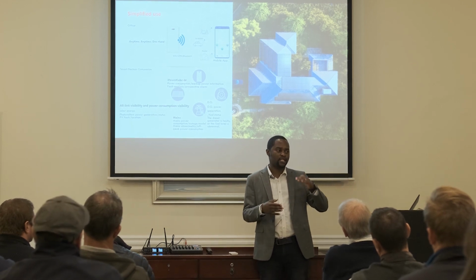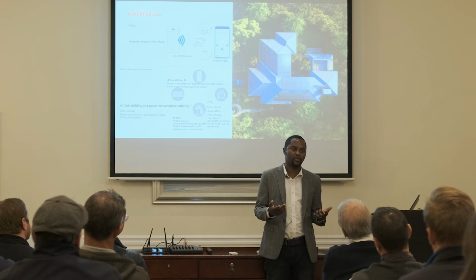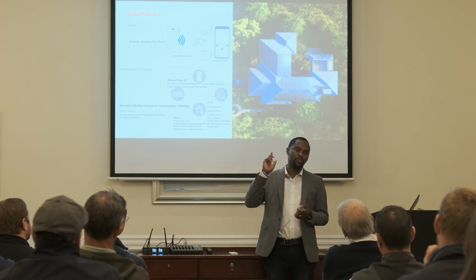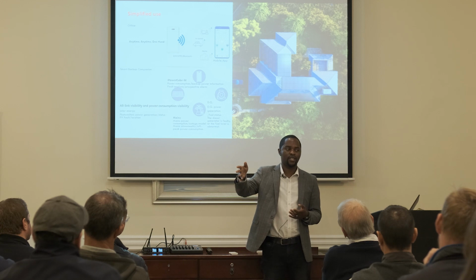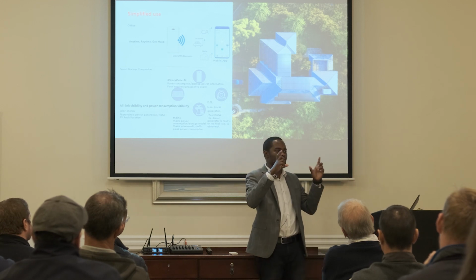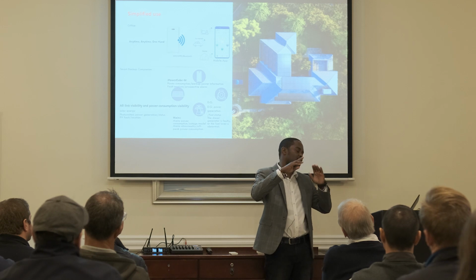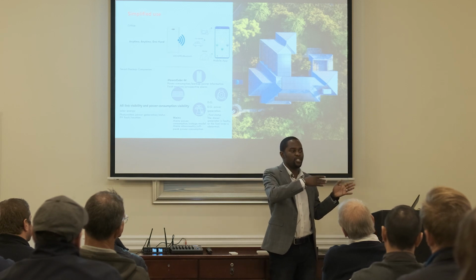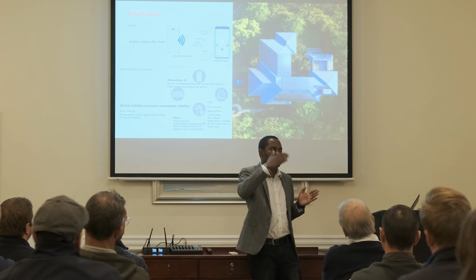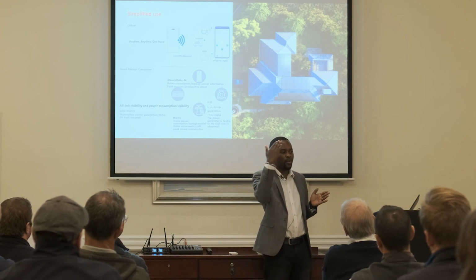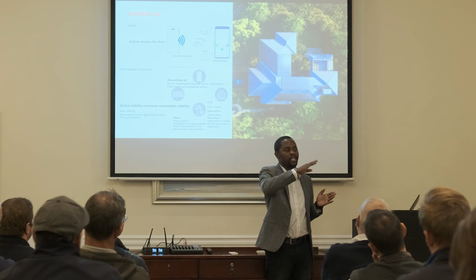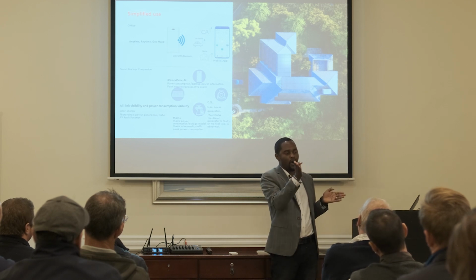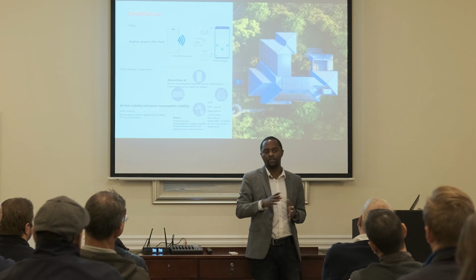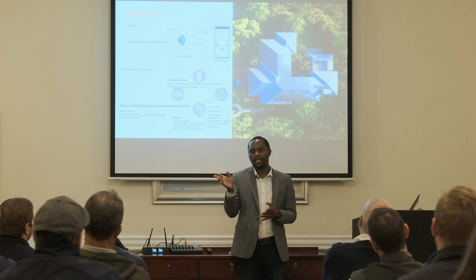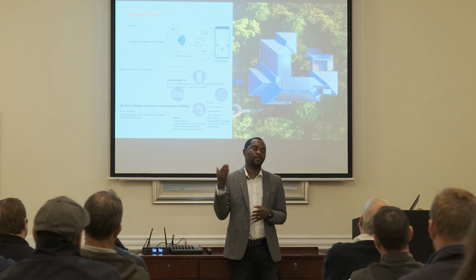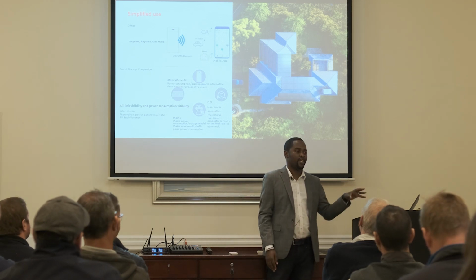But when your battery reaches a certain threshold, let's say 20% or 15%, what you think is lower, then it can give an output that can start a generator, right? So when your generator starts, if you've got an automatic changeover, you've got two inputs: the grid, which you wire as your priority input, then your generator, which you wire as the secondary or backup. So the moment the generator runs, the system will detect that I don't have power here, but I've got power on input number 2. Then the changeover switch, if it's automatic, will automatically change to your generator. Then your generator can supply the loads and charge the batteries.